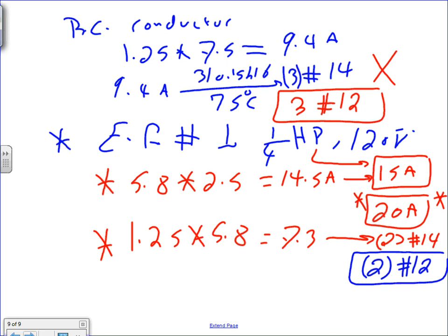So what I would do personally is I up this one to 20 amp and put number 12 conductor and size based on number 12 conductor. And yes, sir. The reason why you do that last step is you already know your breakers. Very good point. Only because it's a motor. Look how we sized that.